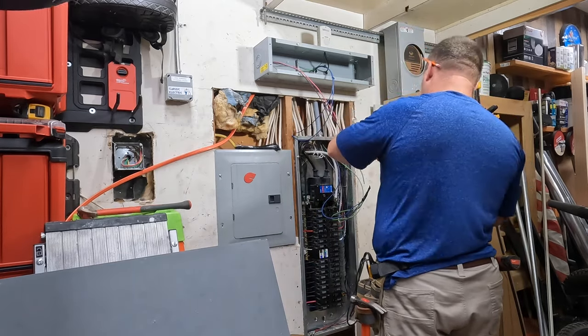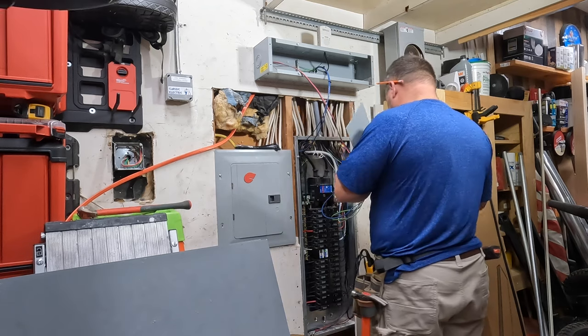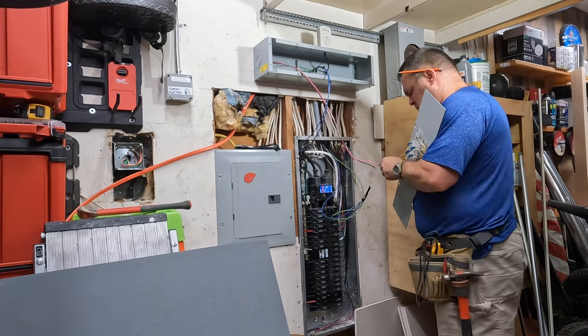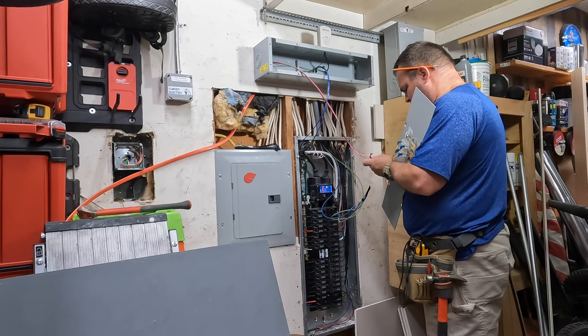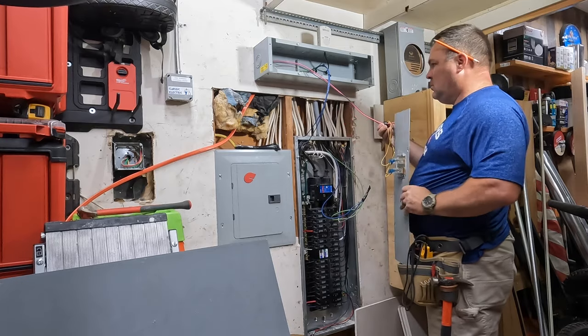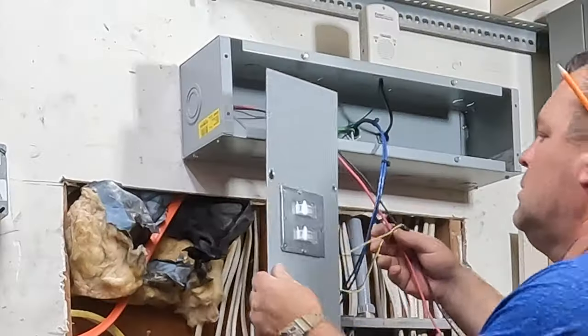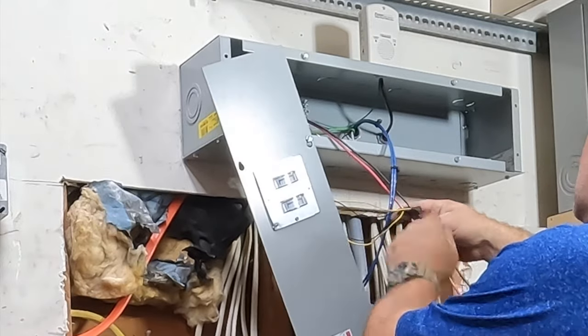Once I get into this wiring trough with that 10-3, I'm going to transition to some THHN, and I ran THHN in that carflex from the wiring trough into the main breaker panel. I'm going to connect it to a 30-amp double pole circuit breaker. That double pole circuit breaker is also mechanically attached to the enclosure.